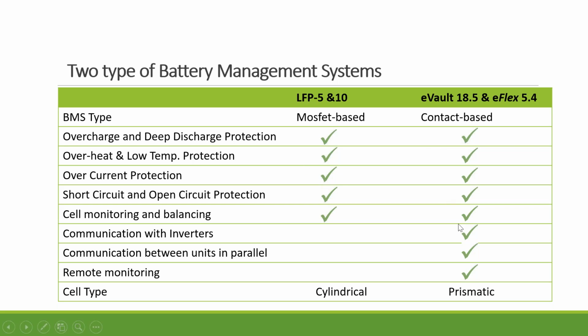In addition to all the protection we just talked about, it also has closed loop communication with the inverter. There's a protocol. Once the inverter and the battery have the same protocol, the battery management system can report the state of charge to the inverter, and it's a much more accurate way of doing so, especially critical for big systems like the eVault. If you stack many of them, then they have this closed loop communication, where it works better.